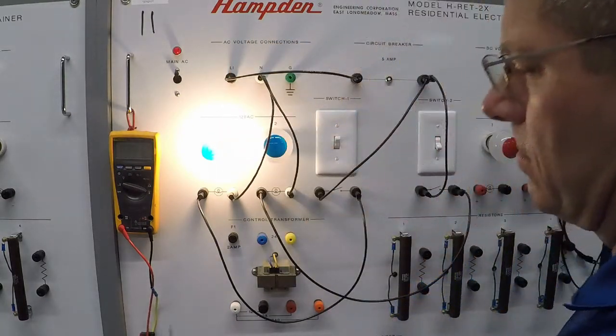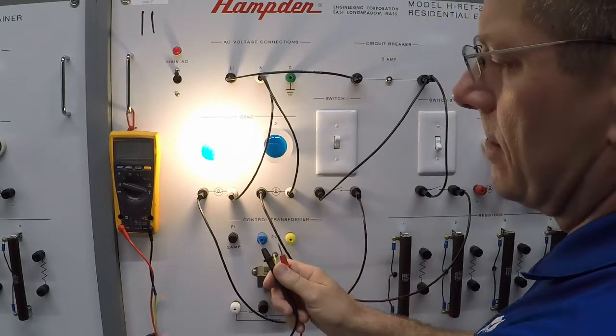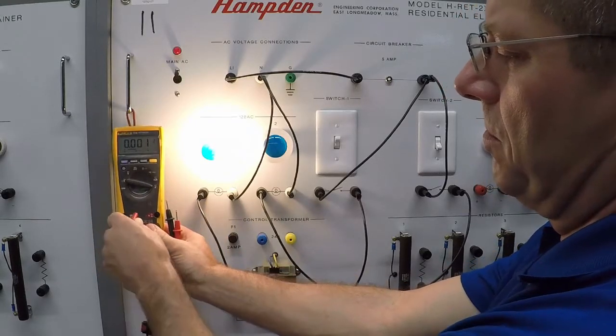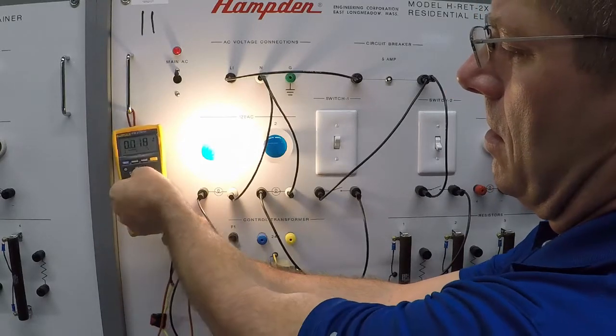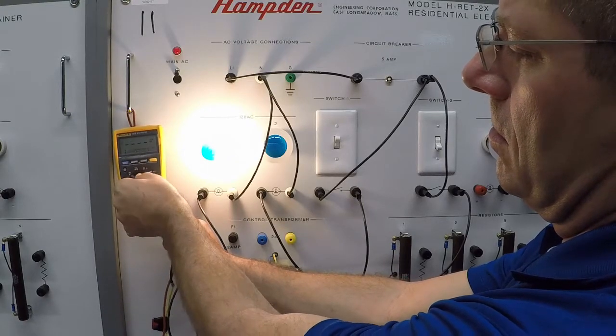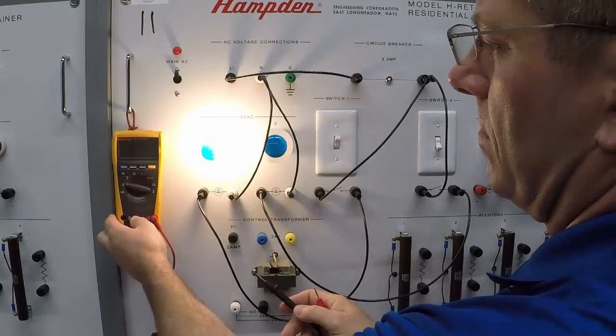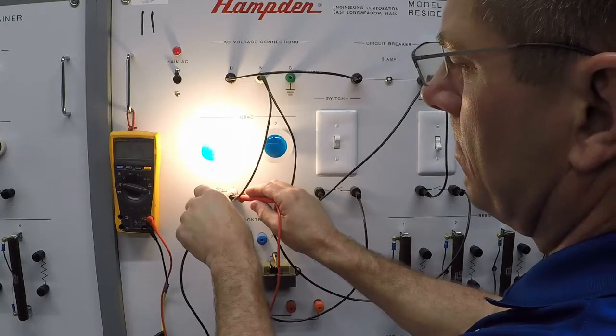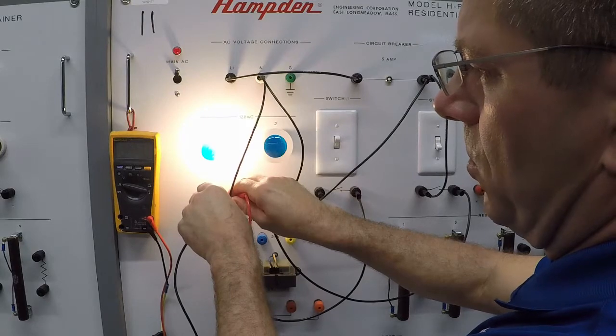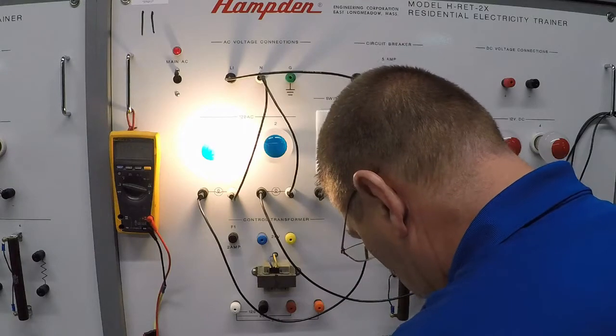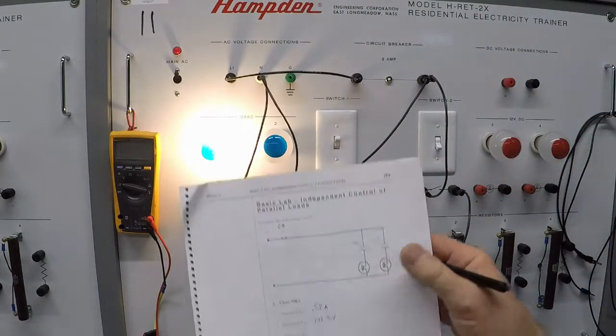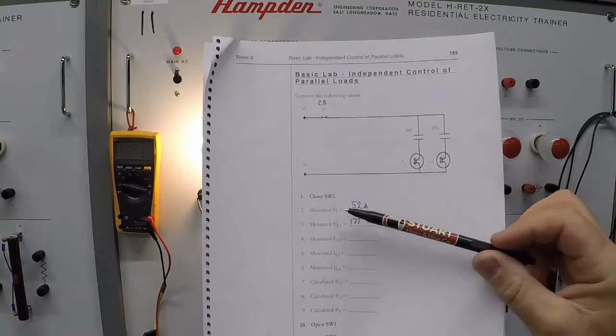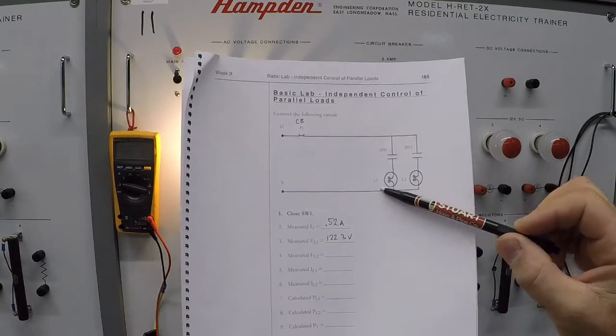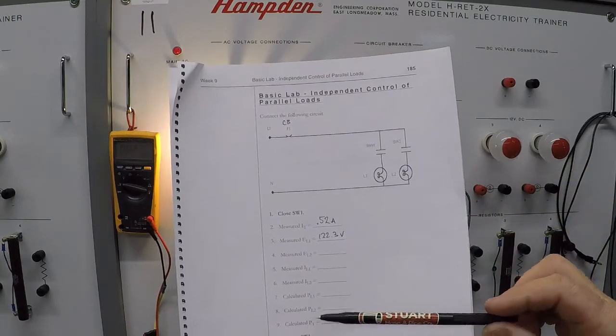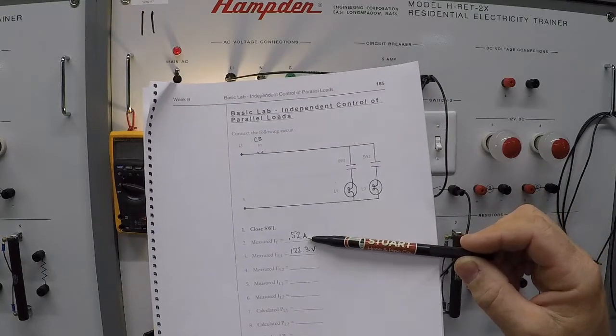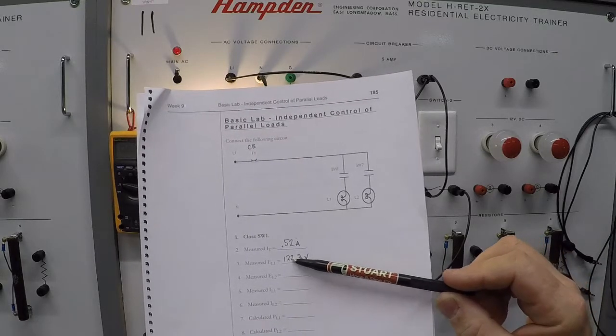Switch 1 is energized. To measure EL1 at step 3, we've got to remember to change the probe position connection. Switch our meter back to AC volts and measure EL1. 122.3 volts. So we've recorded our 0.52 amps for IT, which again is only measuring L1. We have not turned on switch 2, closed switch 2, so we're only measuring L1 current. We measured EL1. In this example, we had 122.3 volts.